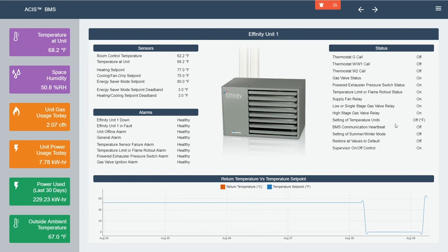One thing we've done as well, because we know that a lot of these are still wired in through thermostats, is we've allowed thermostat calls to be wired in through the BMS interface. So you can wire in a G call, and you can wire in a W and a W2 call for your fan, your heating stage 1 and heating stage 2.